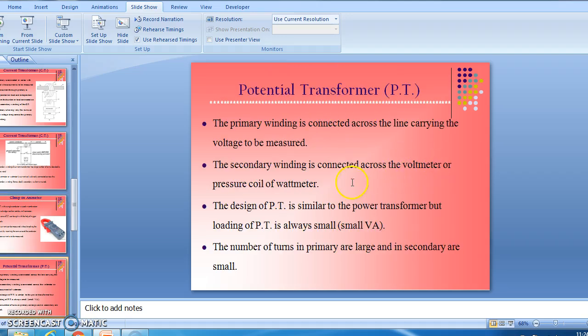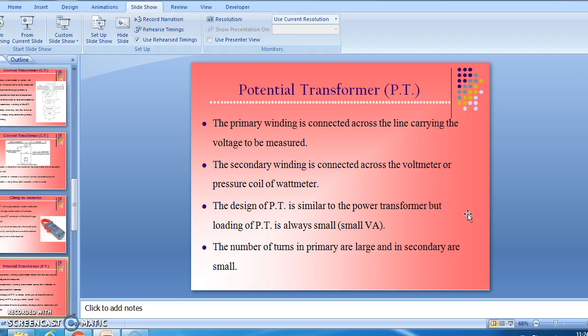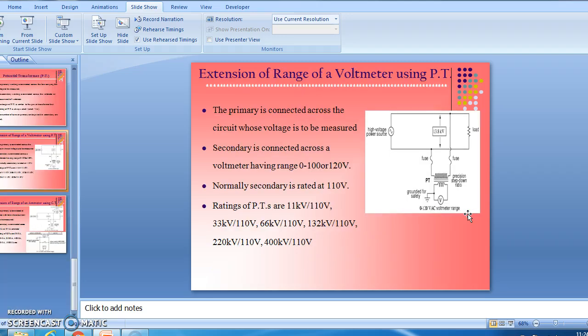In a potential transformer, the primary winding is connected across the line carrying the voltage to be measured, and the secondary winding is connected across the voltmeter or pressure coil of the wattmeter. The design of a PT is similar to a power transformer, but the loading of a PT is always small. The number of turns in the primary is large and in the secondary is small.